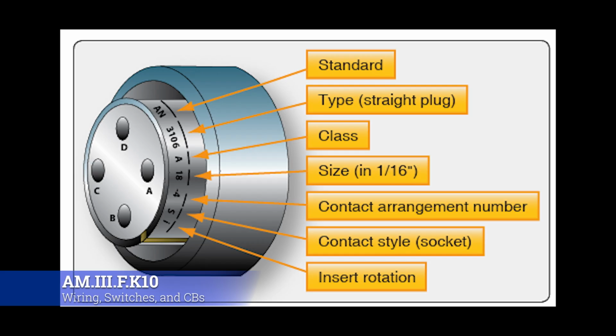Okay, another really common fault point for the power plant electrical system is going to be connectors. Common faults are a pushed pin in the connector - at some point when someone installed it, it pushed the pin, like the collets broke and it came back, or maybe they didn't install it correctly, and it's starting to get pushed back.